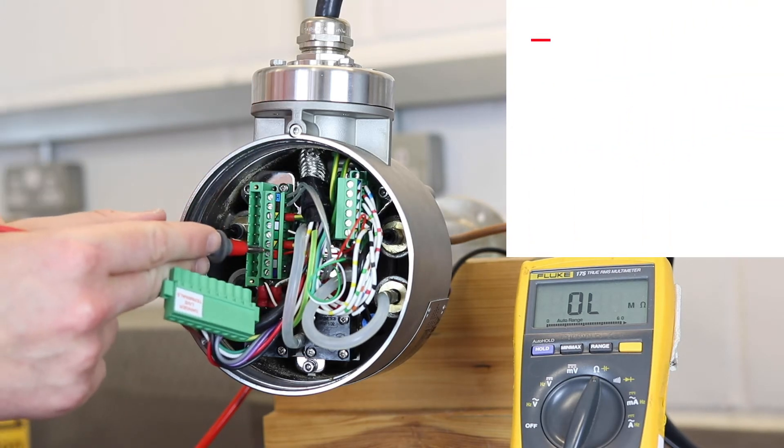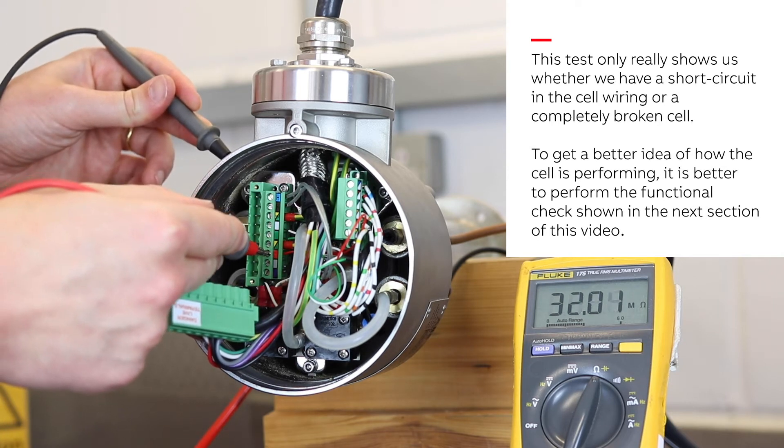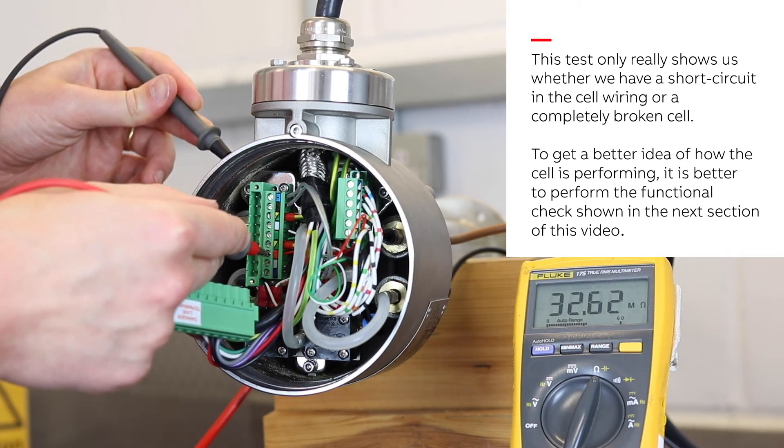We then proceed to the third quick check where we measure the resistance between the red cell plus terminal and the probe body earth. You should see a value way over 20 megohms. If you see a much lower value, check for short circuits to earth in the probe's internal wiring.